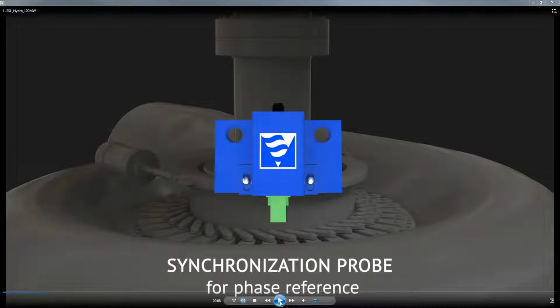The reason for that is that for hydro generators, everything that we measure on the unit, whether it's acceleration, heat, vibration, air gap, flux, axial displacement, whatever we measure, everything is correlated with the rotation of the unit and the number of poles, so that all the information is easily correlated. So the first thing we need is a synchronization probe to give us a signal telling us exactly where we are, how the rotor is positioned when we take readings.